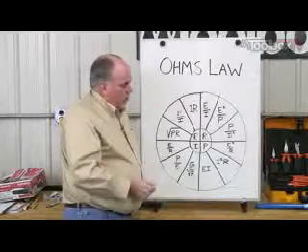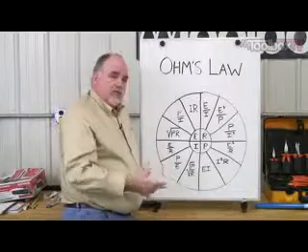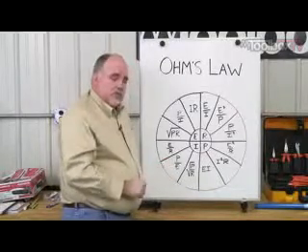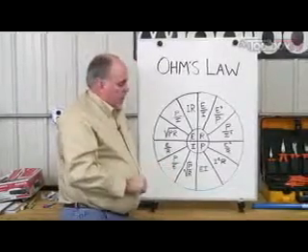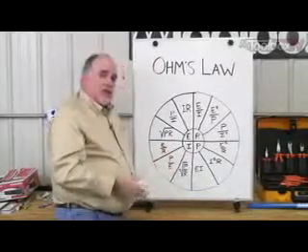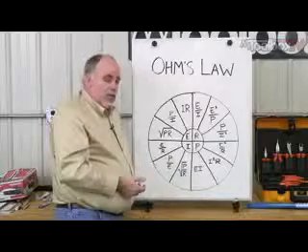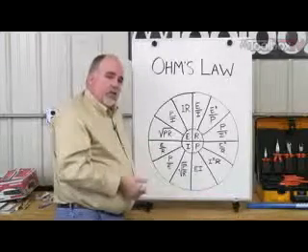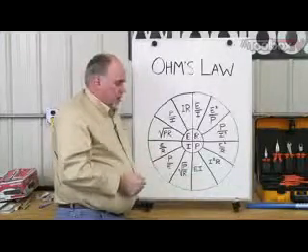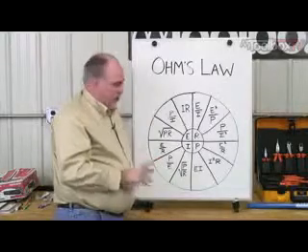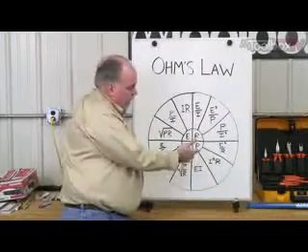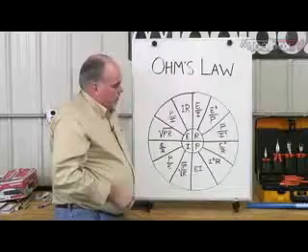And I squared R loss is the heat that you feel built up on an electric motor, or it's a lot of the heat anyway. It would be current squared times resistance, in the case of an electric motor, the resistance in the motor winding. That's the I squared R loss. That heating, it's a loss because you're not getting any work from it. So that would be one of the formulas for power.